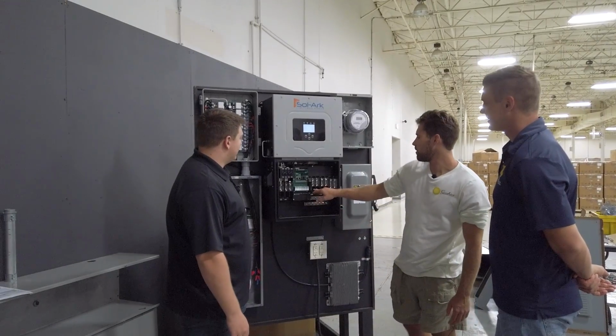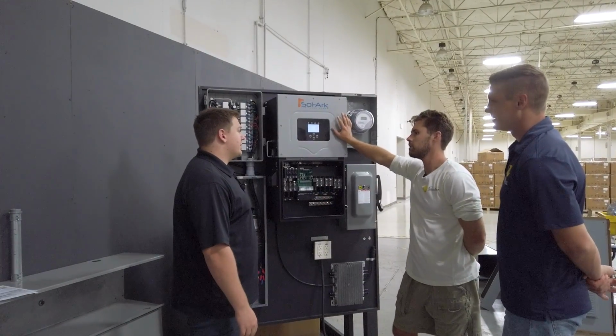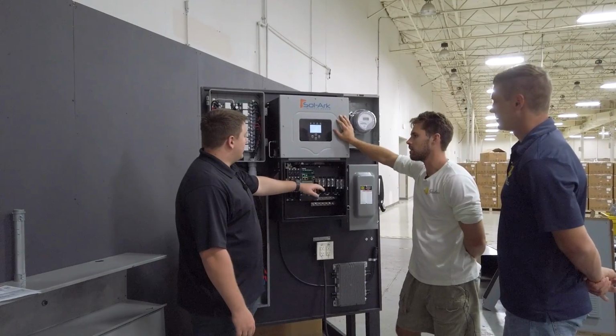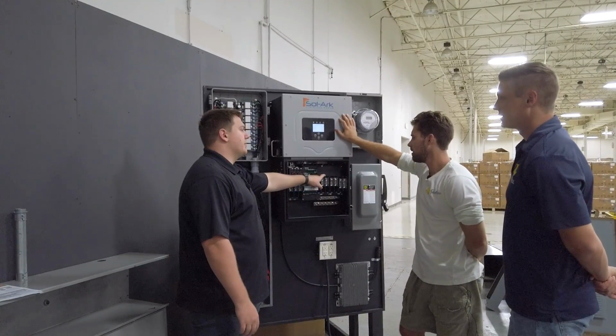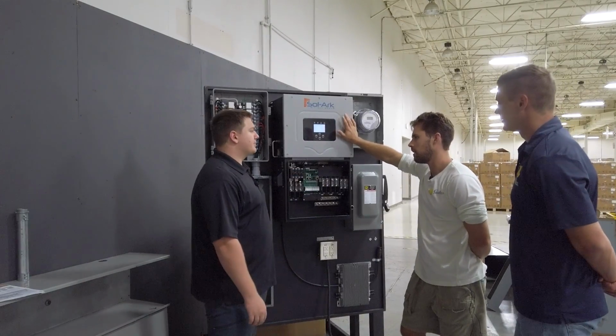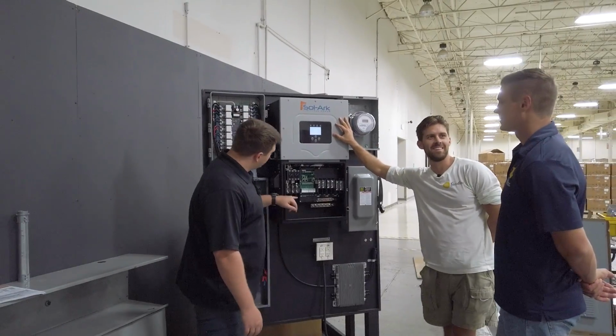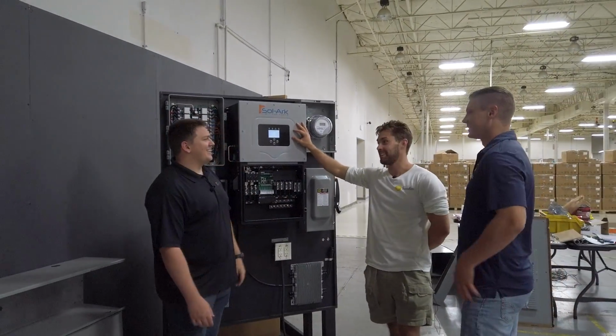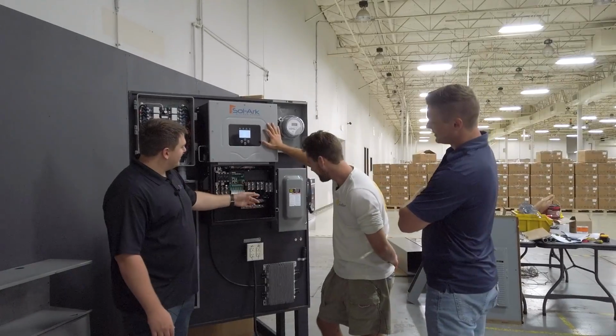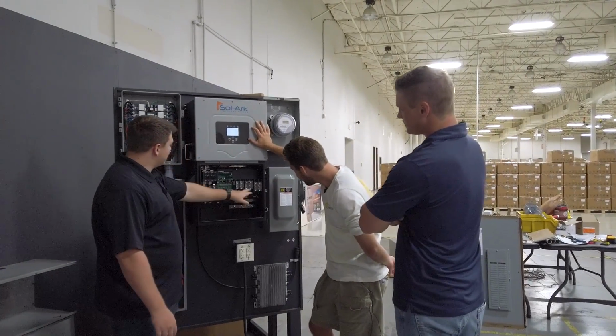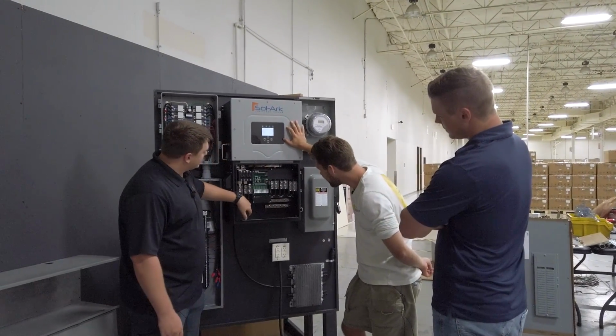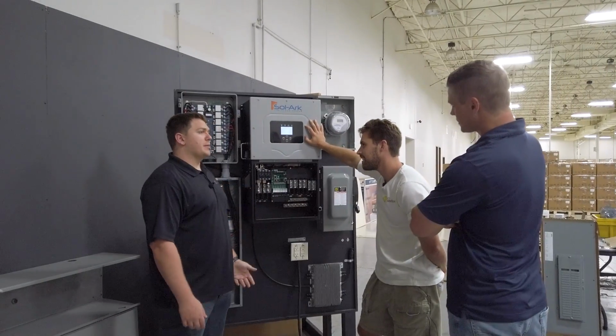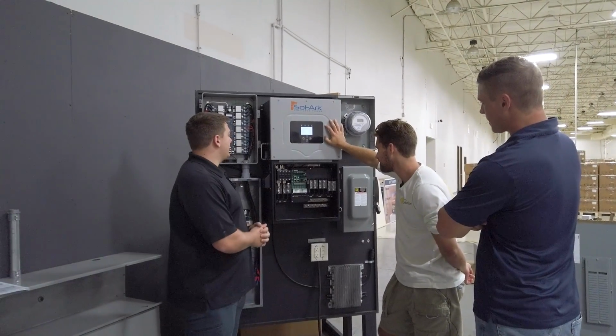And looks like the generator port's bigger. Does that mean we can put a 22 kW Generac in there now? Oh, easily, yeah. This is a 100 amp input for the generator. Really? Yeah, amazing, I didn't know that. So 100 amps on the gen, 200 amps on the grid, 200 amps to the load, and then the battery side we can do 275 amps to the battery, either to or from the battery.